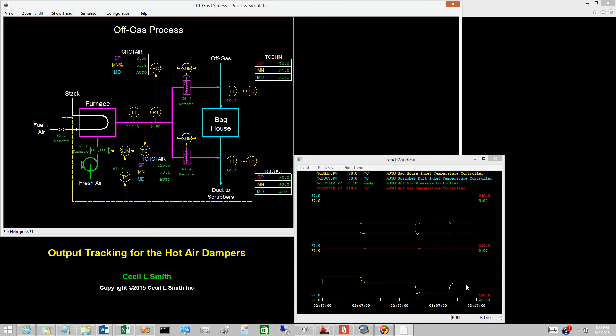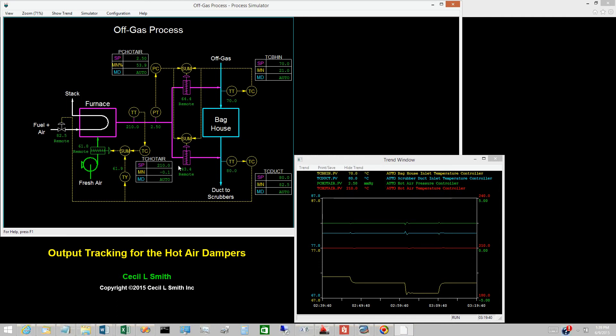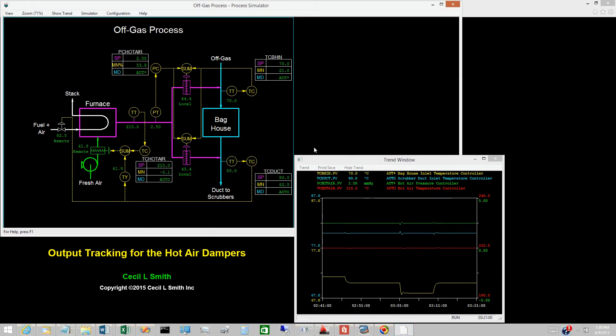Finally, let's illustrate the effect of switching both hot air dampers to local. The order in which they are switched to local is immaterial, so just do it. Now the modes of the hot air pressure controller and the baghouse inlet temperature controller are AUT*, meaning that both are tracking.